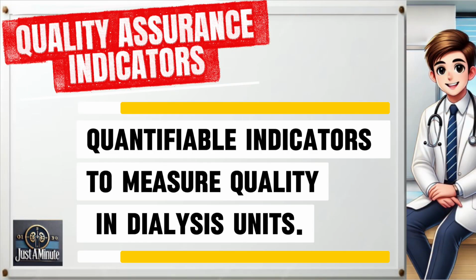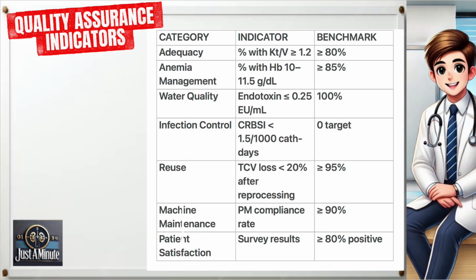Here are examples of quantifiable indicators used to measure quality in dialysis units. How do we measure quality? Through key indicators. For example, we monitor dialysis adequacy with KT over V, aiming for at least 1.2 in most patients. Hemoglobin should be maintained between 10 and 11.5 grams per deciliter. Water quality is tracked by endotoxin levels, which must remain below 0.25 EU per milliliter. We also track infections, like catheter-related bloodstream infections, keeping them below 1.5 per 1,000 catheter days. And finally, preventive maintenance compliance should exceed 90%. By monitoring these indicators, we can ensure patient safety and treatment effectiveness.